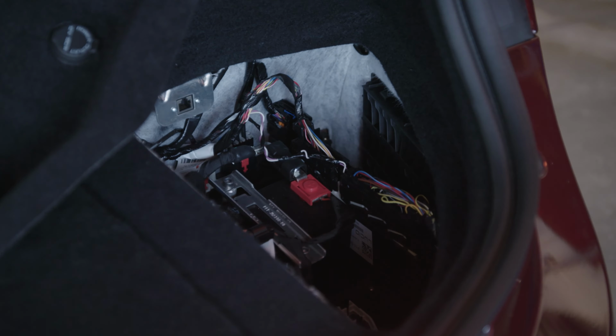If other agents are selected, the only other authorized agents are multi-class extinguishing agents. Foams can produce conductivity, and all other agents that produce encapsulating characteristics can prevent the battery from freely burning, but they will not stop thermal runaway or actively cool the lithium-ion battery cells. So the resulting consequence is a prolific buildup of toxic and flammable gases that are captured within the encapsulating agents. They eventually hit a temperature where they breach the encapsulating agents, are released in a fuel-rich gas cloud, lean out as they induct fresh air, and then produce explosivity. So the application of agents other than water can result in an explosive environment as opposed to a controlled burning characteristic with a flammable environment.